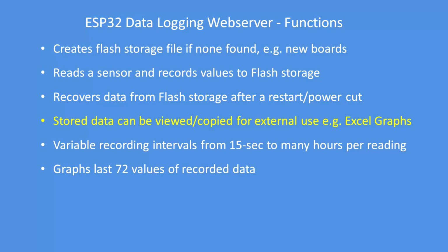recording ability. Stored data can be viewed and copied for external use, so you can view the log file and then copy out and into Excel, where you can enhance the graphics and graphing and analyze the data. Data logging recording intervals can be varied from 15 seconds the minimum up to many hours per reading. You can graph the last 72 points of data, so the time base will be a function of your recording interval. The duration is a limitation of Google Charts. That's as long as I can make it.